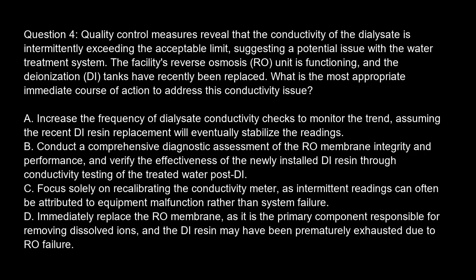Question 4. Quality control measures reveal that the conductivity of the dialysate is intermittently exceeding the acceptable limit, suggesting a potential issue with the water treatment system. The facility's reverse osmosis (RO) unit is functioning, and the deionization (DI) tanks have recently been replaced. What is the most appropriate immediate course of action to address this conductivity issue?